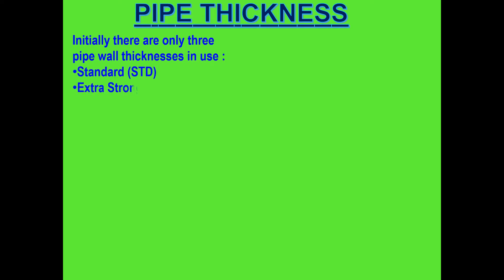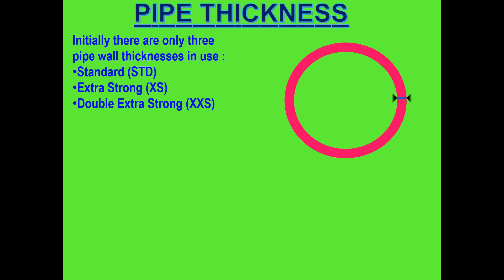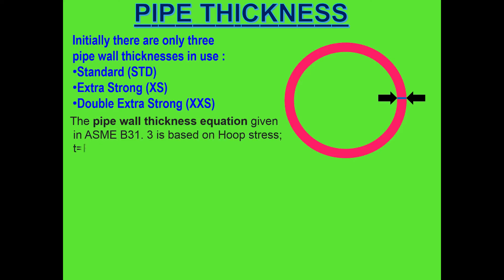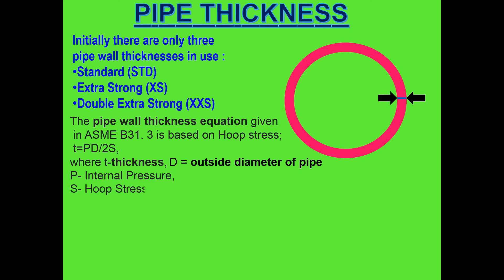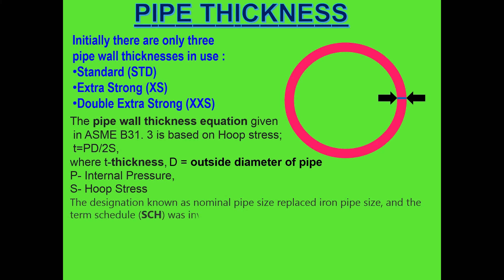Next we see about pipe thickness. Initially there are only three pipe wall thicknesses in use: standard (STD), extra strong (XS), and double extra strong (XXS). The pipe wall thickness equation given in ASME B31.3 is based on hoop stress: T = PD / 2S, where T equals thickness, D equals outside diameter of pipe, P equals internal pressure, and S equals hoop stress.